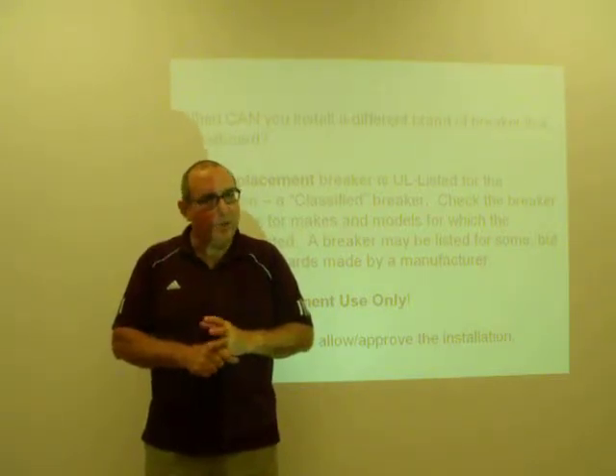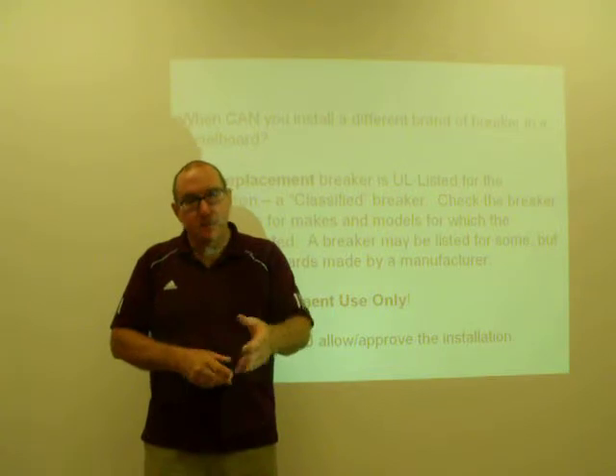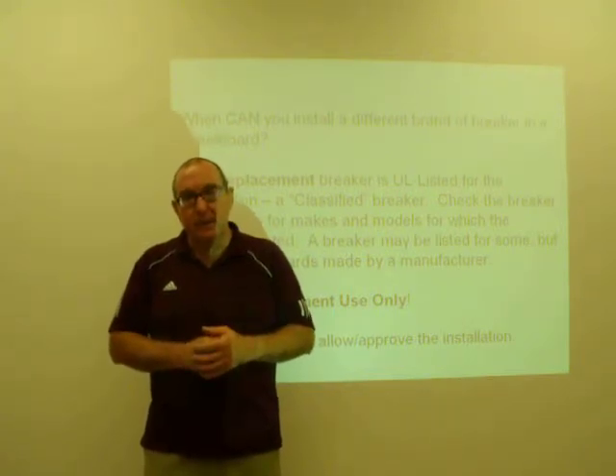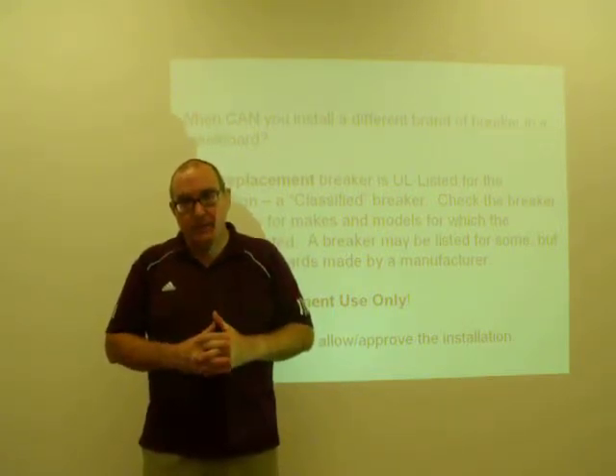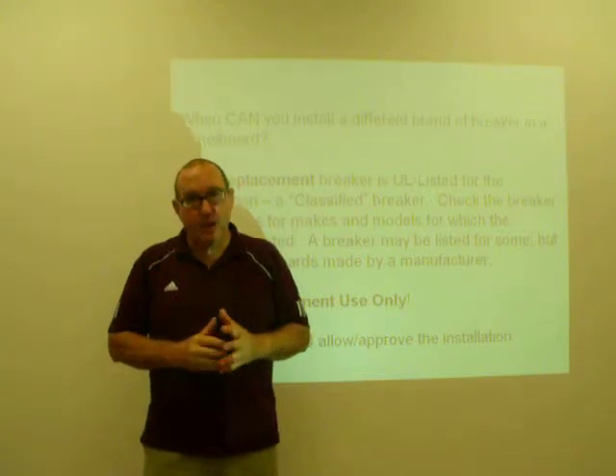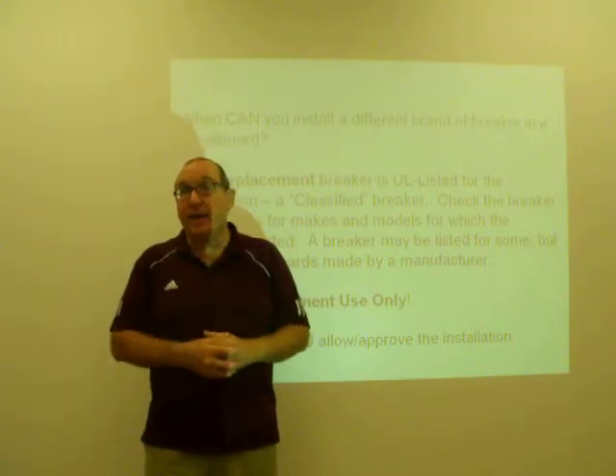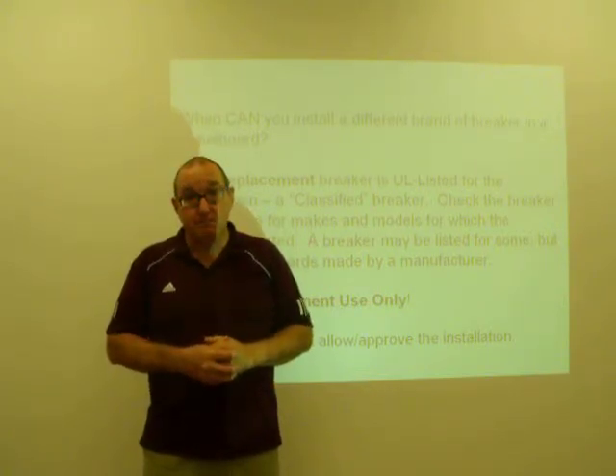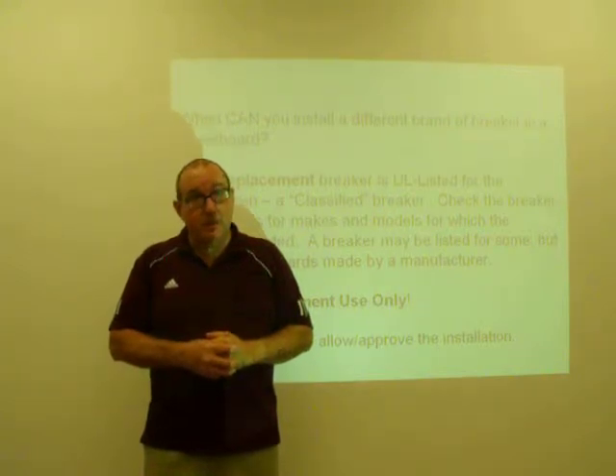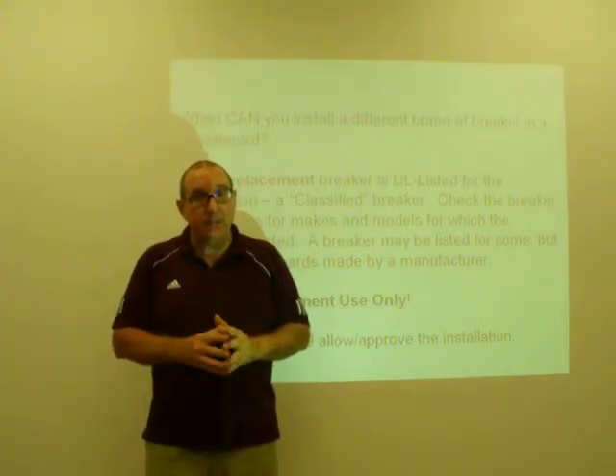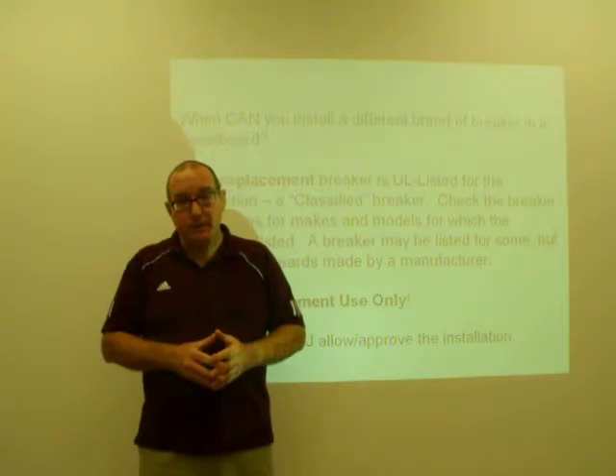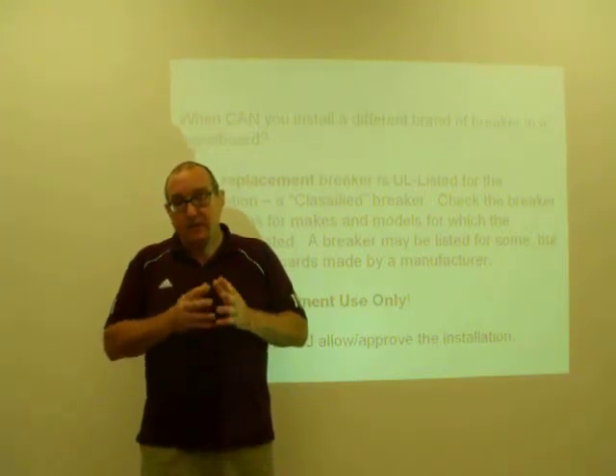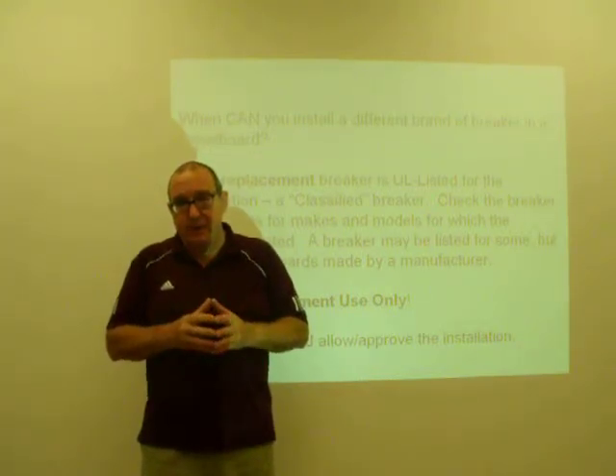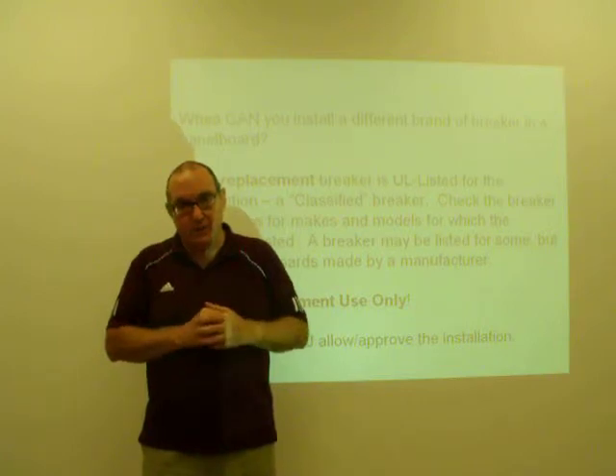But a lot of people don't want to do that because it costs them time and money. That's why they do the field modifications, or they try to jam a breaker that really isn't meant to go in there into that panel board, or just use any other breaker they happen to have on their truck that might fit. The other option is you can carry a limited supply of what are called classified breakers. Now, generally speaking, you're not allowed to use classified breakers for original installations.